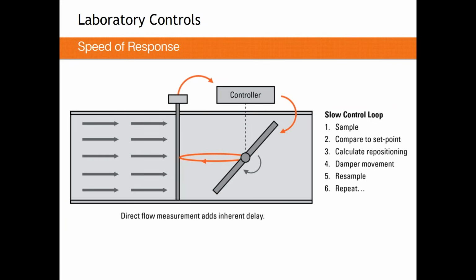But really what we're measuring here is, from the time we introduce a change in sash position, how long does it take us to get back to the required airflow? So from the time I start opening the sash or the time I stop opening the sash, how long does it take me to get to the required airflow? Generally speaking, there are 3 ways to do that. You can start at the start of sash movement, you can start basically in the middle of the sash movement, or you can start at the end of your sash movement.